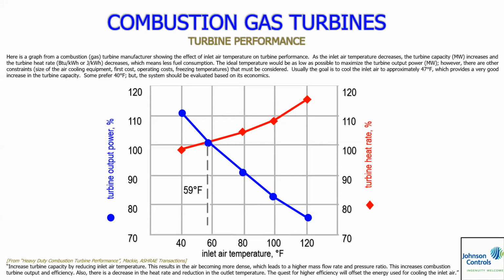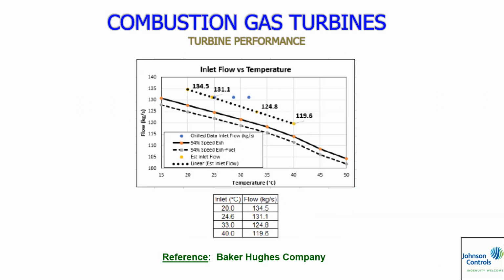Now, when you look at this chart here, what we're seeing is the inlet air temperature reducing; look what's going on with your turbine output. It's increasing. See what's going on here? Now, ISO, remember it's 59 degrees is the normal rating point. So if you can cool that air down, two things are going on. Your turbine output increases. This is your net heat rate. It's decreasing, less fuel. So you can have your cake and eat it too. You're increasing capacity and reducing fuel consumption. So see what's going on here? Now, for my friends at Baker Hughes, here's another way to look at it. Temperature, now this is in Celsius, okay, with flow in kilograms per second. As the inlet air temperature is reducing, look what's going on with the flow. It's increasing. Remember, if you increase the flow, you get more capacity out of the turbine.